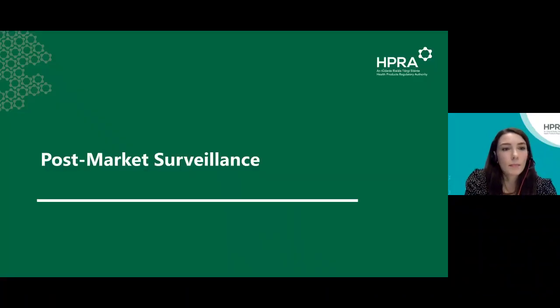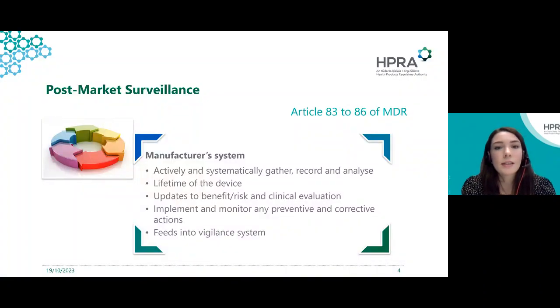So then starting with post-market surveillance. Essentially the MDR requires that manufacturers conduct post-market surveillance, which is covered under Articles 83 to 86 of the MDR. This is how you would review the experience gained from the use of the device and take all necessary corrective actions. A formal post-market surveillance system involves active and systemic collection, analysis, and interpretation of data or other information about a marketed device.